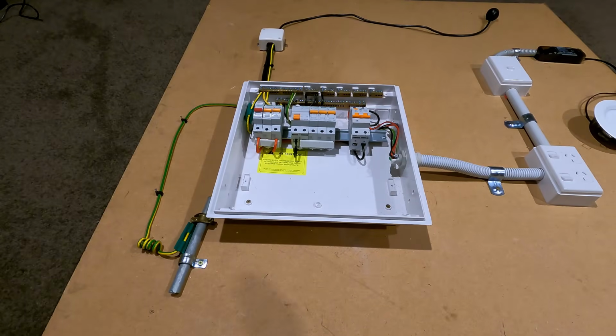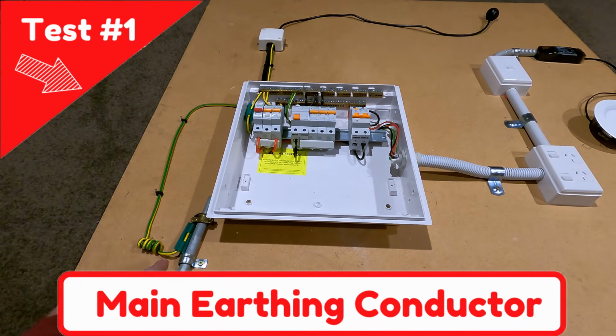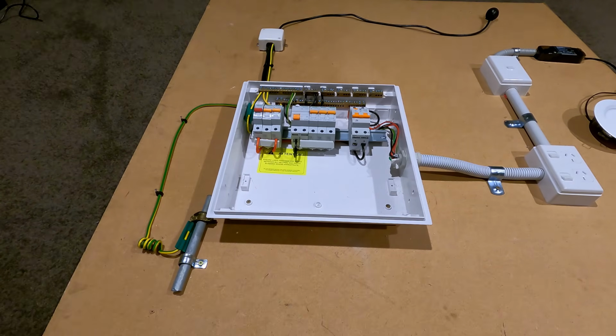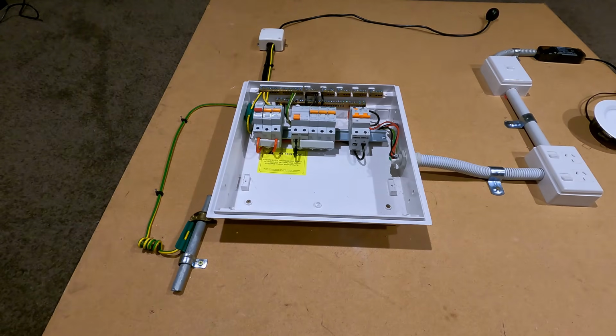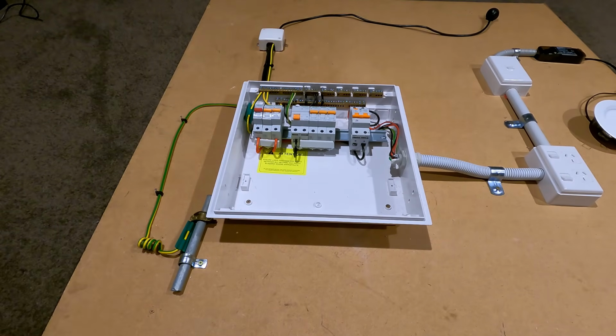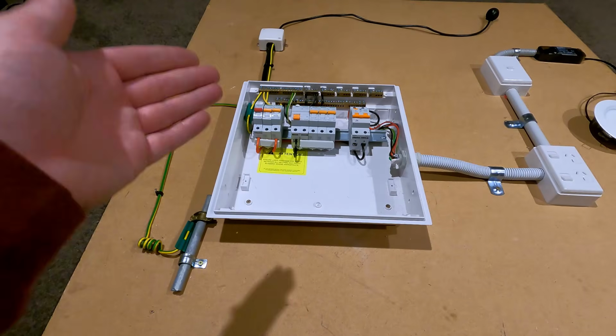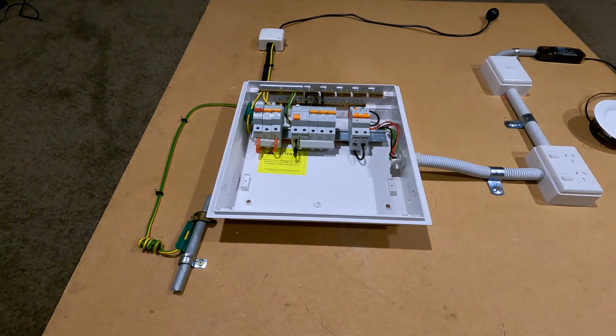Sweet, so now we get on to mandatory testing. So the first thing in the system that we want to test is the main earthing conductor continuity. So between the earth stake and the earth bar there. Obviously, the switchboard and the main earth are going to be quite a fair distance away from each other. Not like in this video where I've got the liberty of having the main earth right next to the main earth bar, so I can easily just test between the two using the meter leads. It's not going to be like that in practicality.